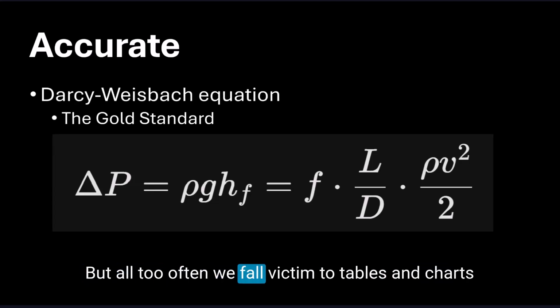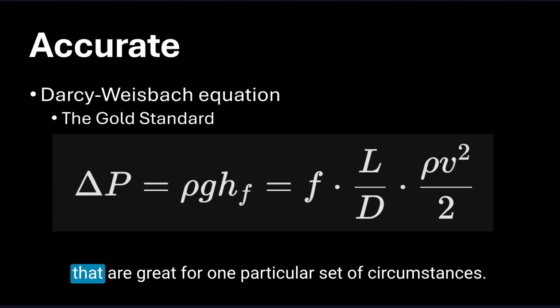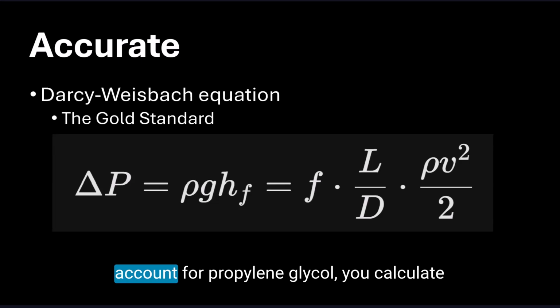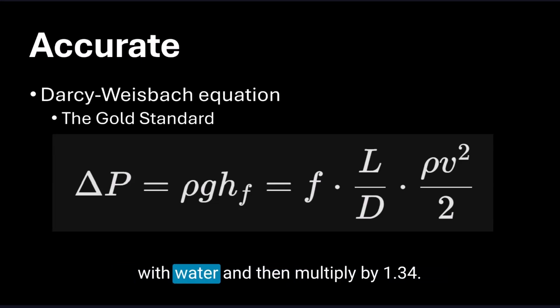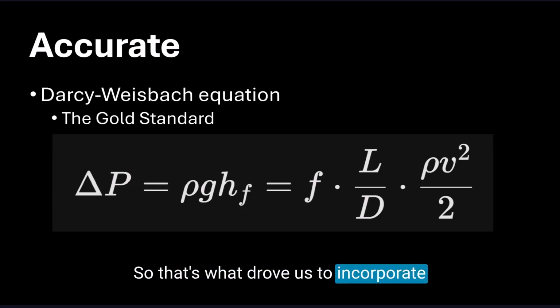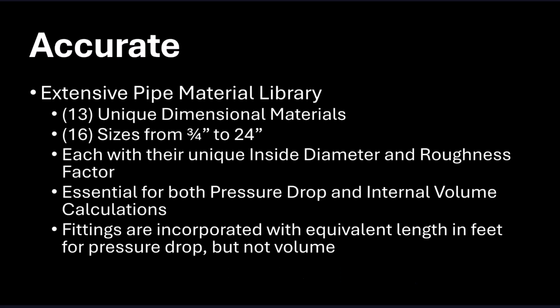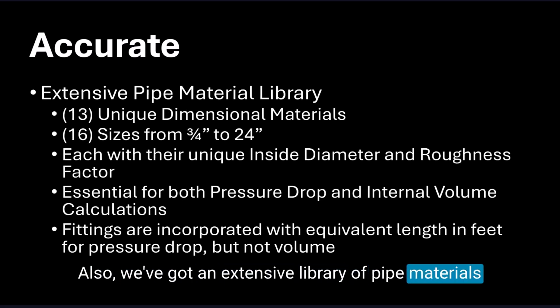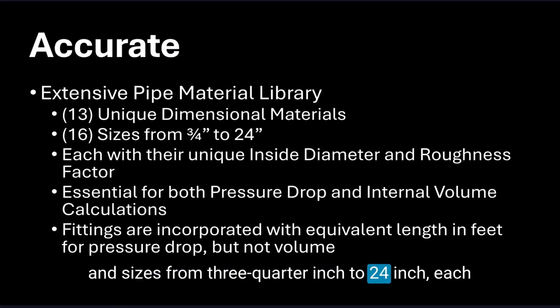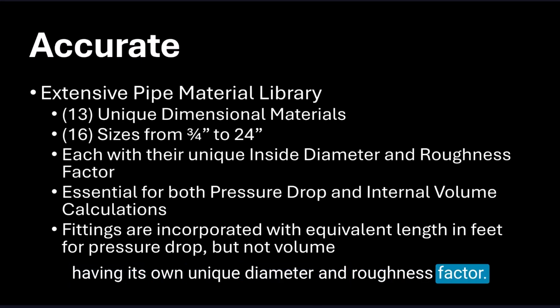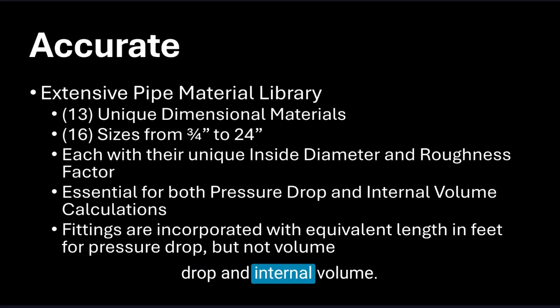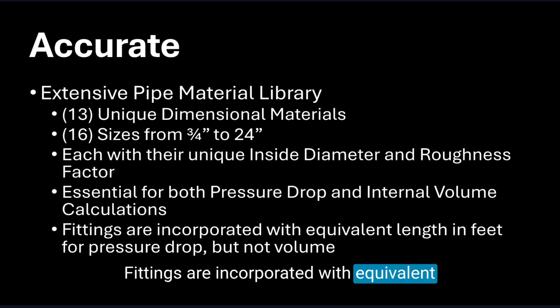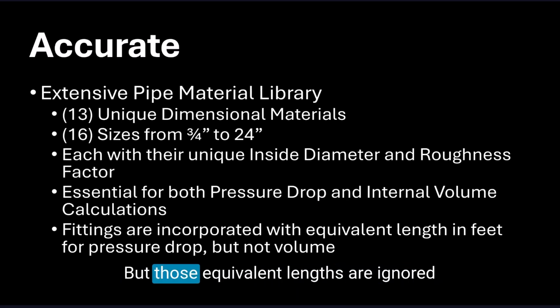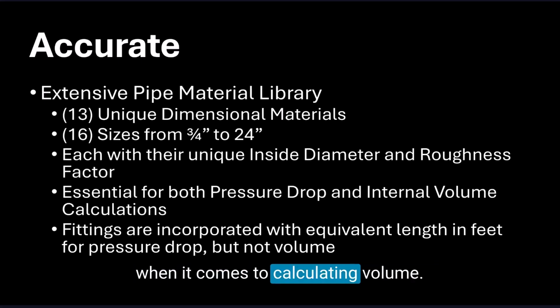But all too often, we fall victim to tables and charts that are great for one particular set of circumstances. Like I was taught by IGSHPA that to account for propylene glycol, you calculate with water and then multiply by 1.34. I don't think that's accurate enough. So that's what drove us to incorporate this kind of logic into our software. Also, we've got an extensive library of pipe materials and sizes from 3/4-inch to 24-inch, each having its own unique diameter and roughness factor. These are essential for pressure drop and internal volume. Fittings are incorporated with equivalent length, thanks to Galen's feedback, but those equivalent lengths are ignored when it comes to calculating volume.